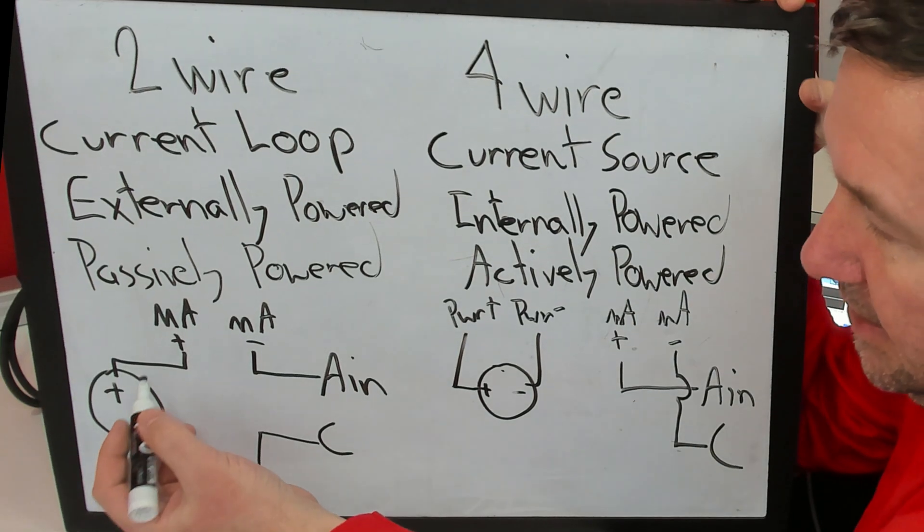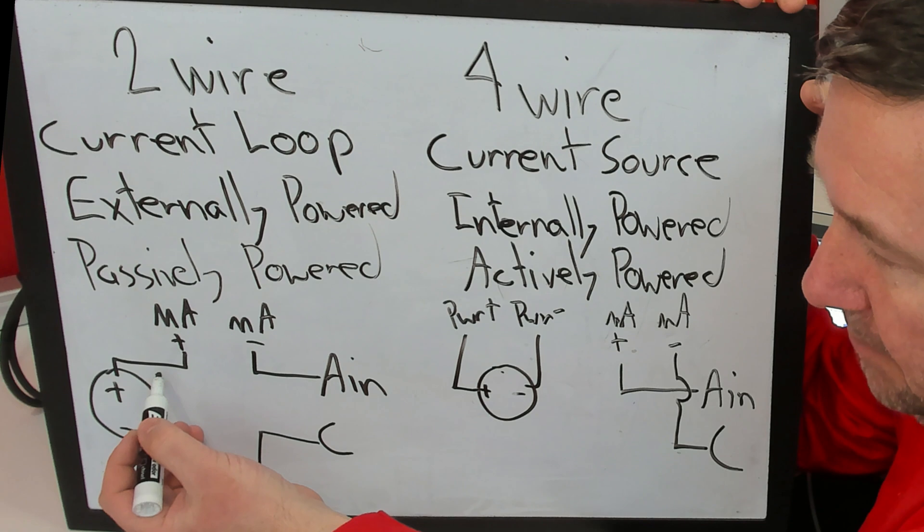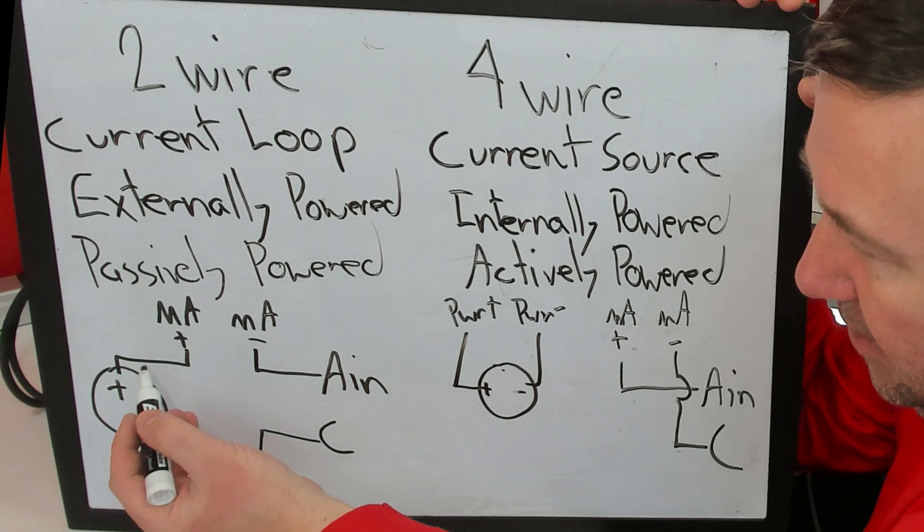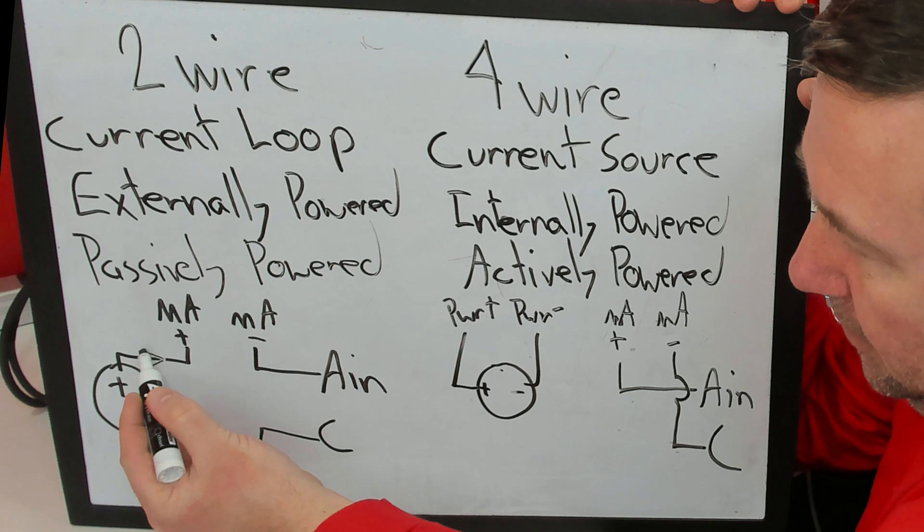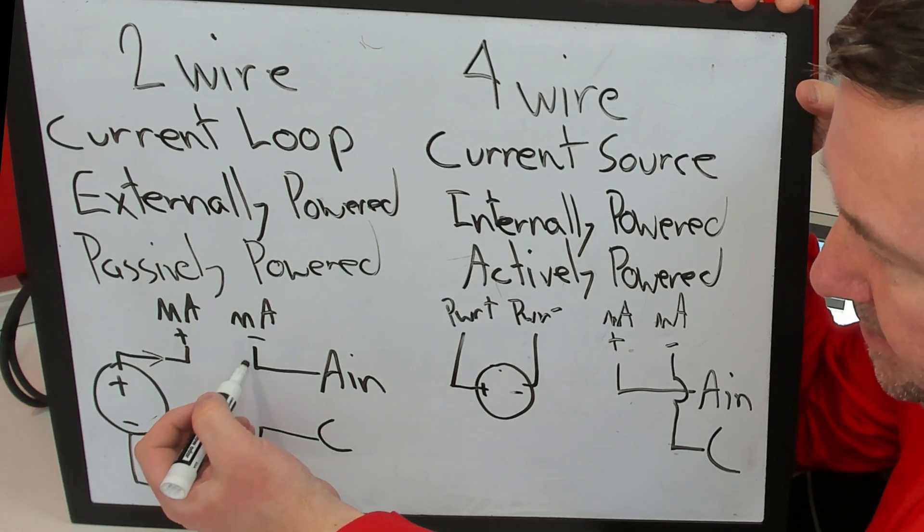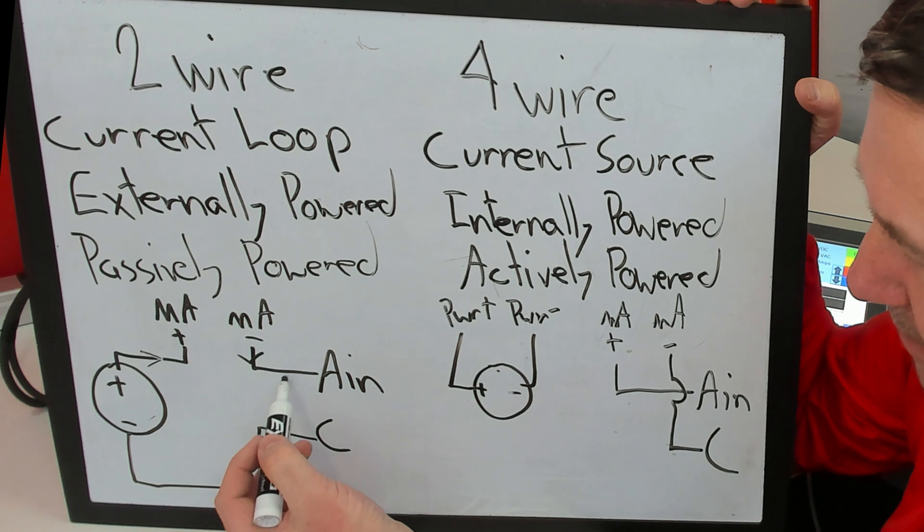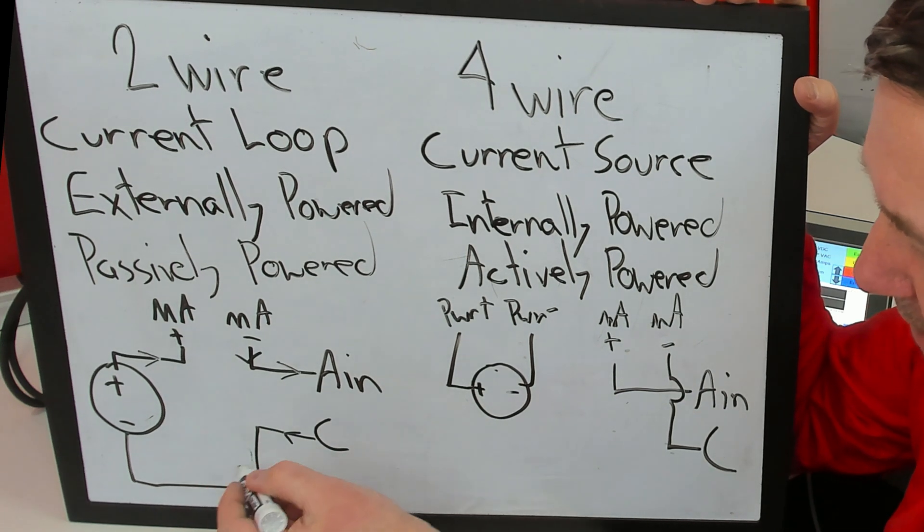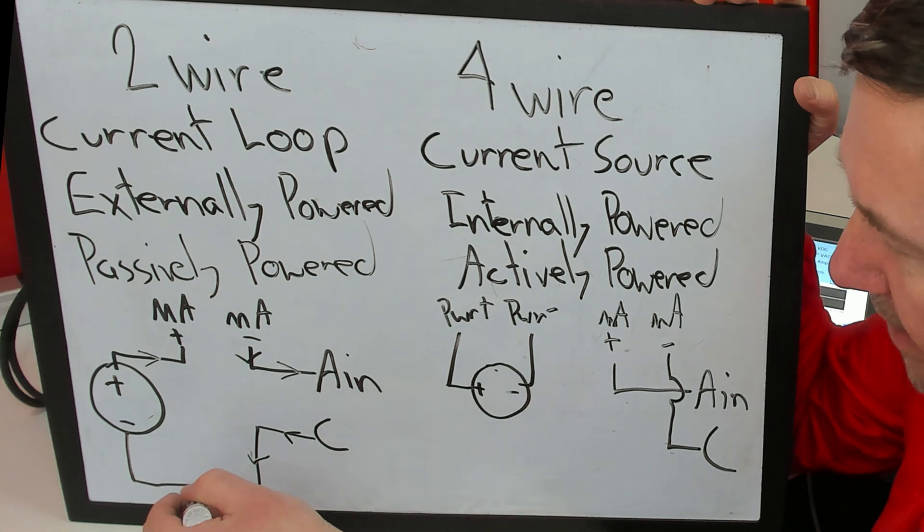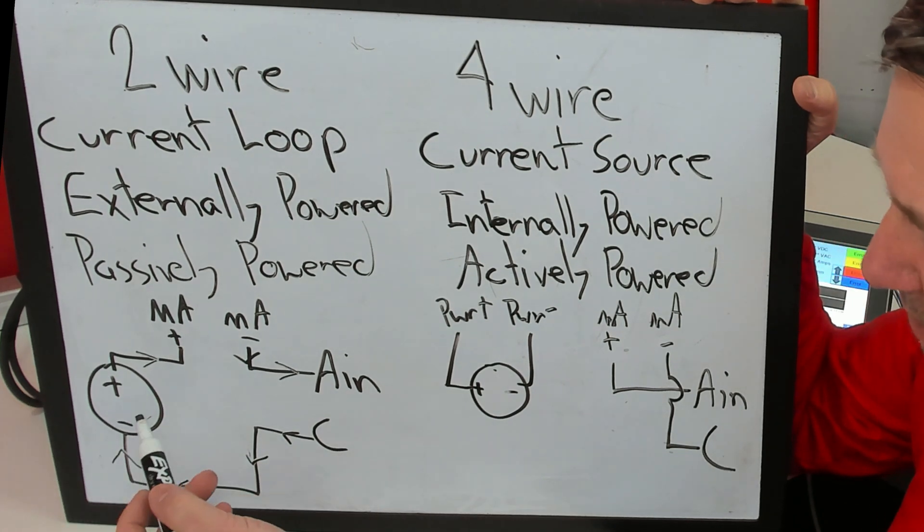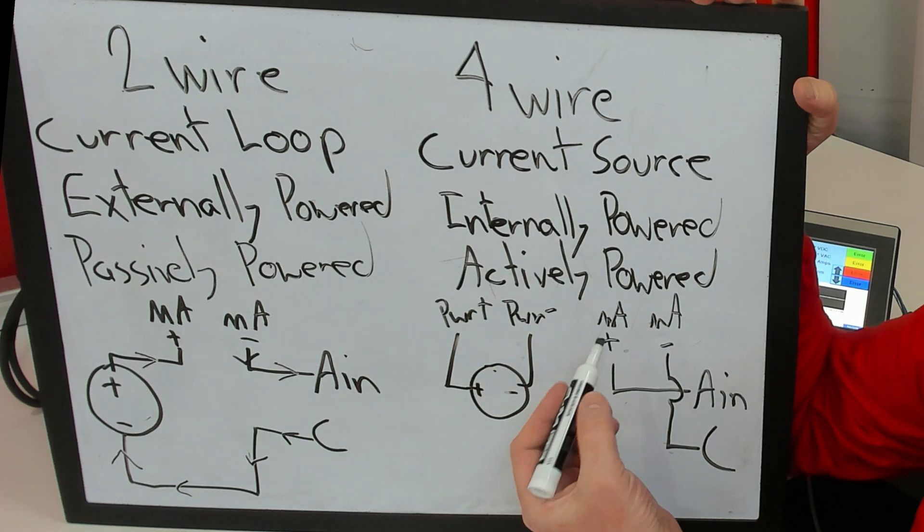So if we take that positive power is coming out of our power supply, such as conventional electron flow, it's going to flow out of the positive, into the milliamp plus, out of the milliamp minus, to the analog in, out of the common, and back around to the minus of our power supply.